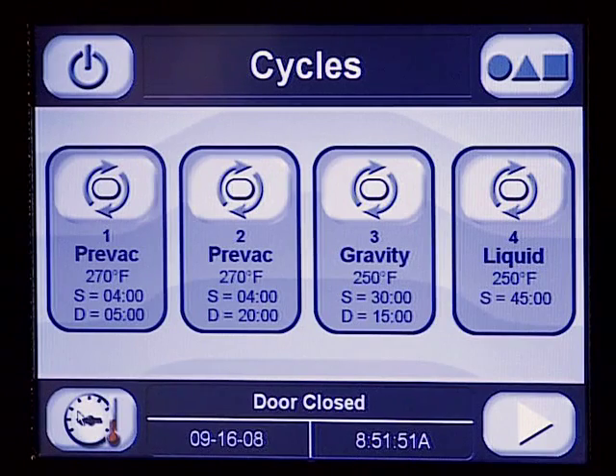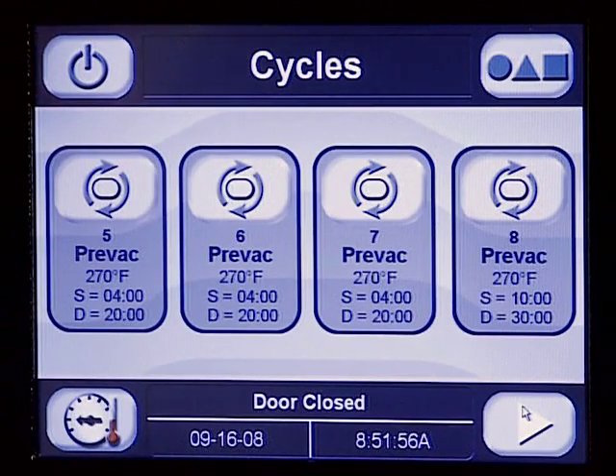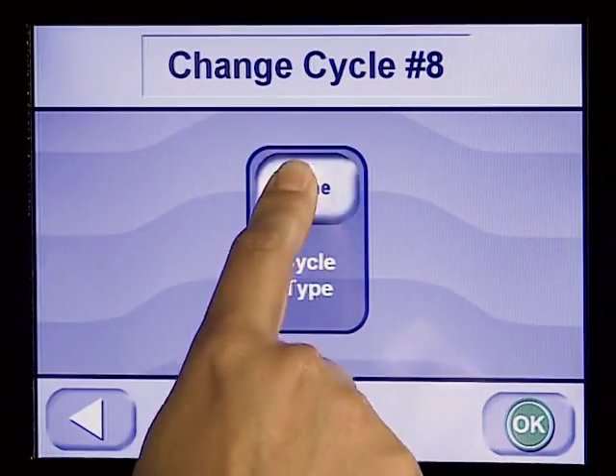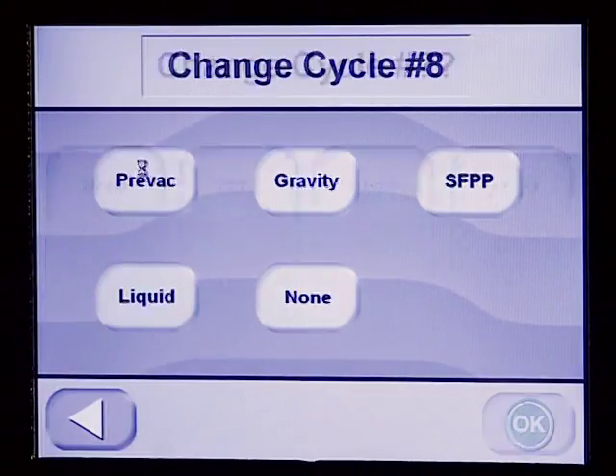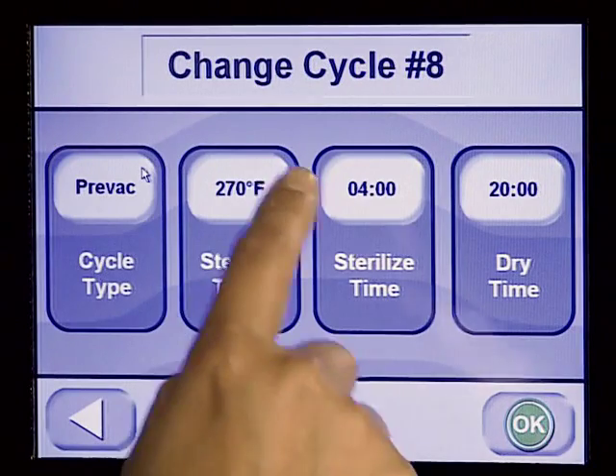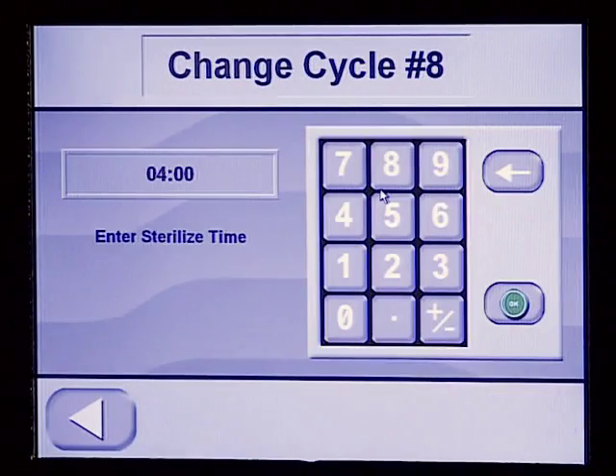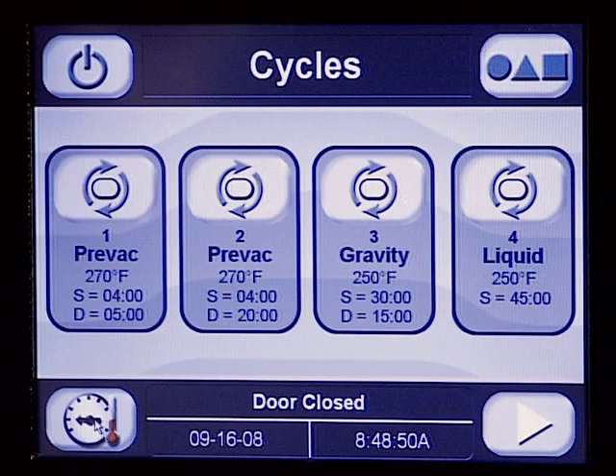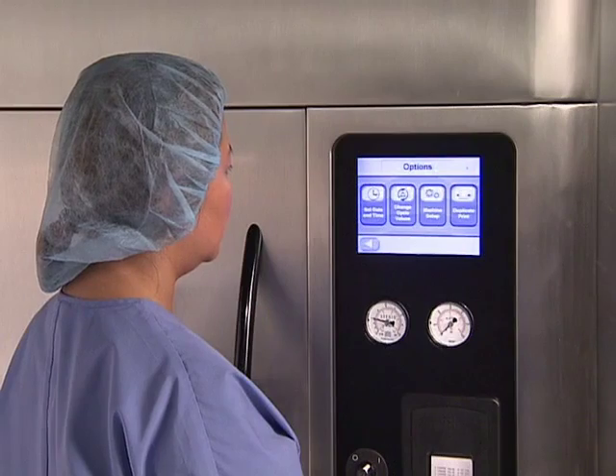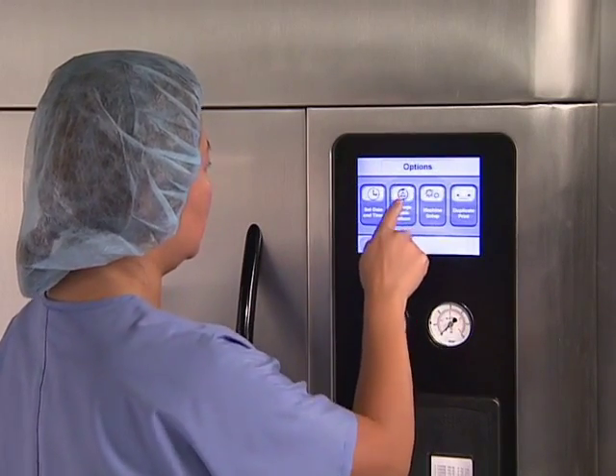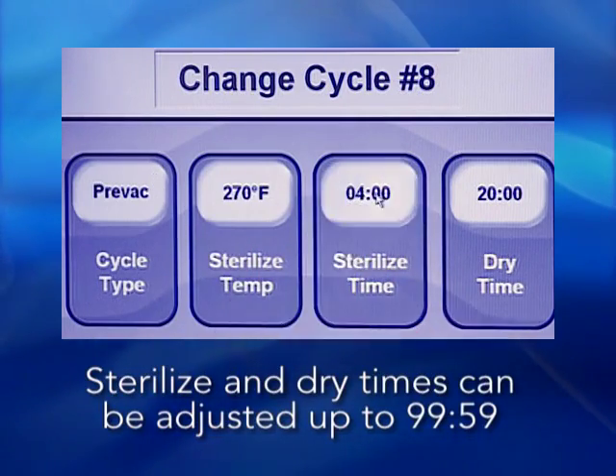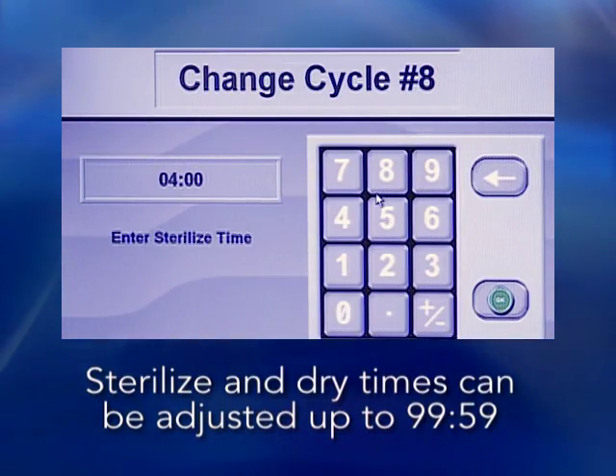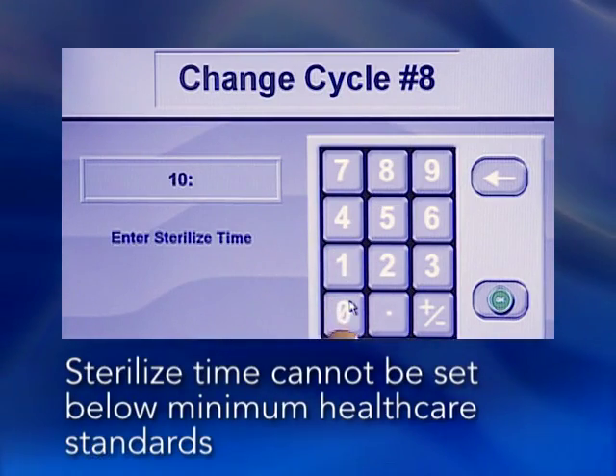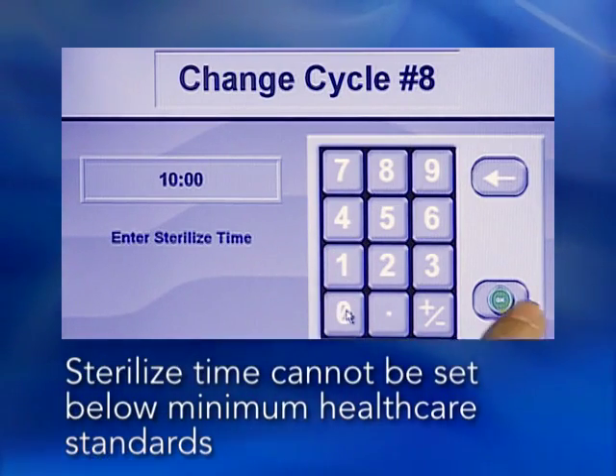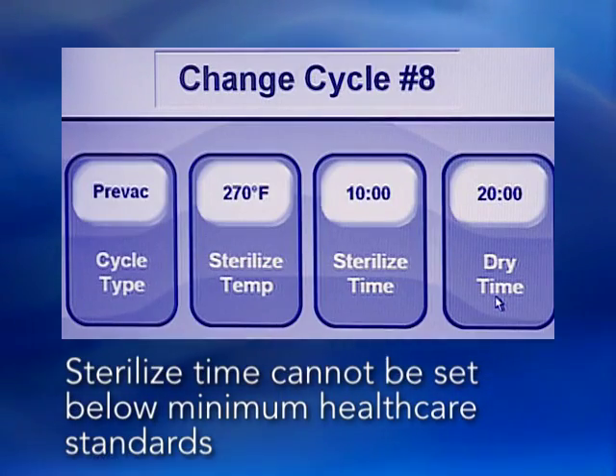As mentioned earlier, this sterilizer comes with a set of pre-programmed cycles that comply with all relevant healthcare standards. However, cycle temperatures, sterilization times, and dry times can be changed to meet specific instrument manufacturer reprocessing instructions. You can also choose which cycles are displayed on the main control panel display and change the sterilizer settings. Sterilize time can be adjusted upward to a maximum of 99 minutes and 59 seconds. But neither time nor temperature can be adjusted below the minimum values recommended by healthcare standards.